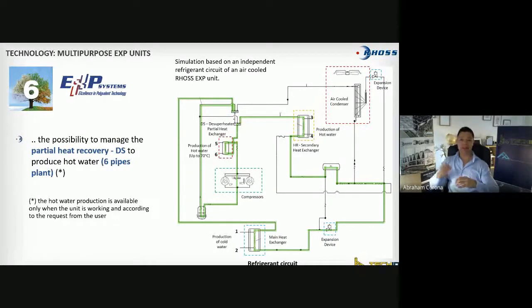That means, for example, if the compressors for any reason are working in partial load, you're probably going to get different temperatures than 70, or maybe lower. So this is a plus, but it's something that is difficult to control. It's not something that I want you to rely on. Yeah, I want to have that. I'm going to have 45 kilowatts at 70 degrees. So it is something to keep in mind.